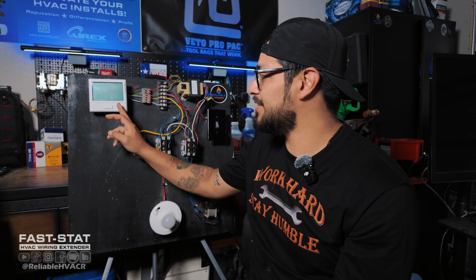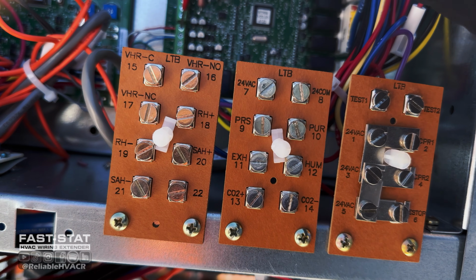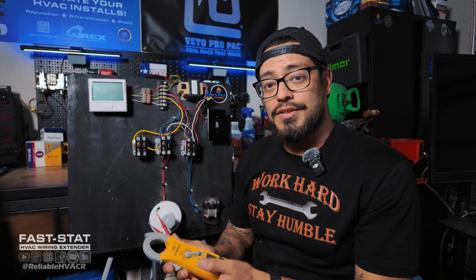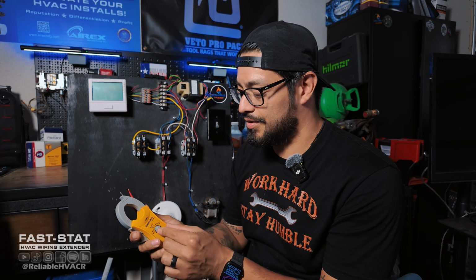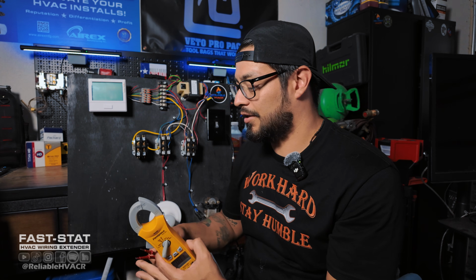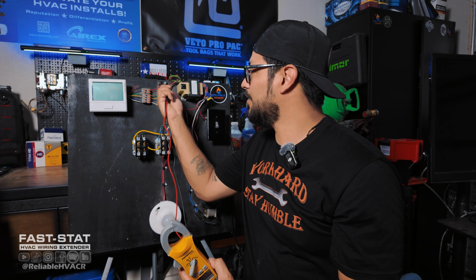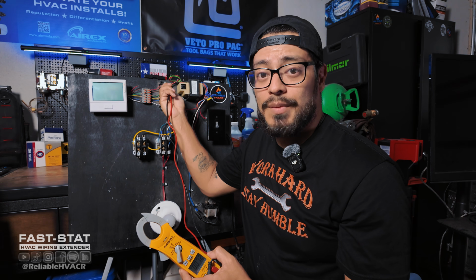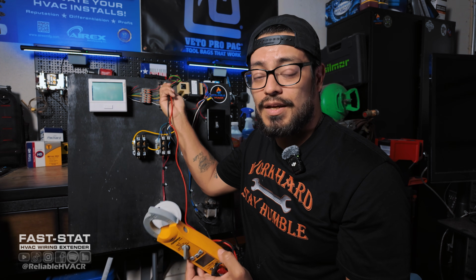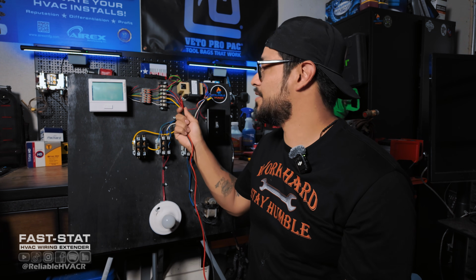So wherever this lands on a terminal board or control board, whatever it is, that's where I typically go to check voltage. All you're going to do is grab a meter. The Fieldpiece ones are pretty good. You can get a basic one, or go to Home Depot and get a Klein or Milwaukee. They do HVAC meters now, so you can go pick one up. Basically, you're going to check your R to common and make sure that you have 24 volts. That's your first step. If you don't, obviously, you need to go look at your fuse and transformer.